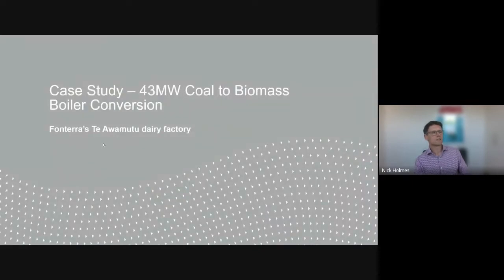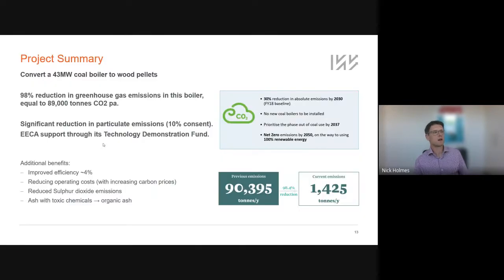So the next case study is a 43 megawatt coal boiler conversion. So it was an old boiler. When I say old, it was probably 10 or 15 years old. It was one that Windsor supplied to Fonterra. So it was originally a coal boiler. They have had a lot of lignite cheap coal for thermal generation.